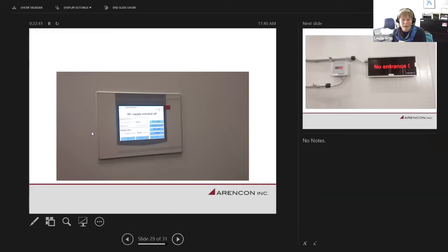On the control panel, they do have a display screen with operator controls. At this point you'll see it shows the oxygen level. We weren't running the system at the time, this was before we brought in the conditioned space, so you'll see the sensors reading the ambient air at 20.2. It says that the nitrogen is switched off. So that's at the operator controls back at the control panel.